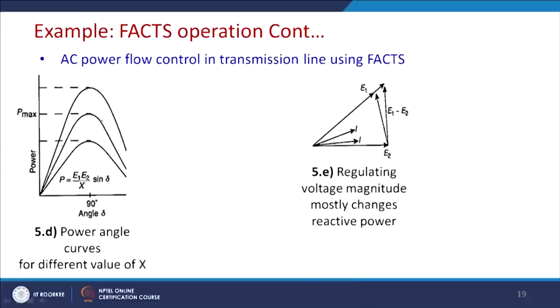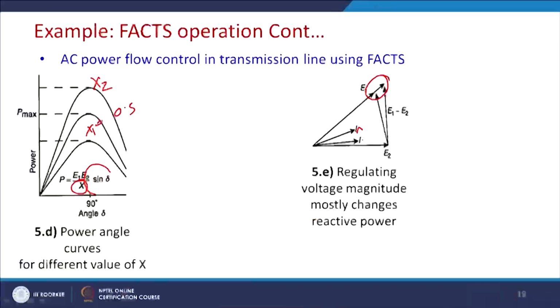Since E1 E2 by X sin delta is a curve, if you increase or decrease the value of X, subsequently for X1 you will get this one, and for X2 you will get this one, where X equals 0.5. So, this power handling capability is ultimately governed by the thermal and other stability issues of the system. In the same way, we can inject voltage in phase. It can easily be done by a tap changing transformer, and thus the value between E1 and E2 changes, reactive power as well as real power can be changed, and the current changes from I1 to I2.